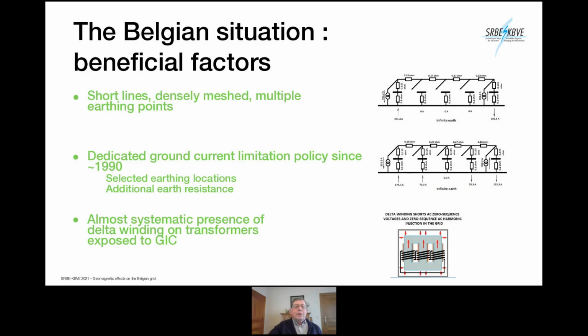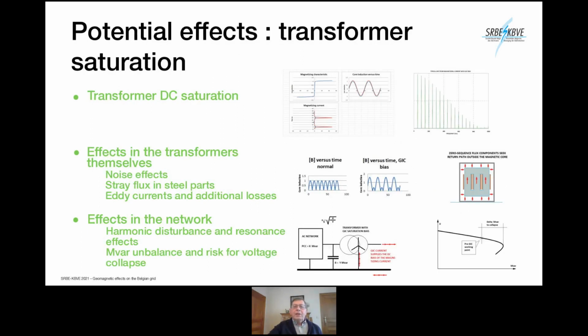Another effect you see on the left. In the transformer, the flux, which is normally thought to stay in the steel core, will, due to saturation of the core, leave the steel core and permeate into the oil, into the tank, into the windings, and everywhere where it should not be. And this has two effects. The steel parts, which are normally not subject to alternating flux, will heat up by magnetic heating and also by eddy currents. And then in the windings, the additional flux creates additional loss.